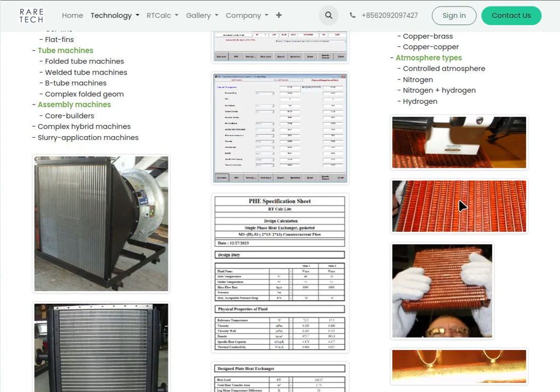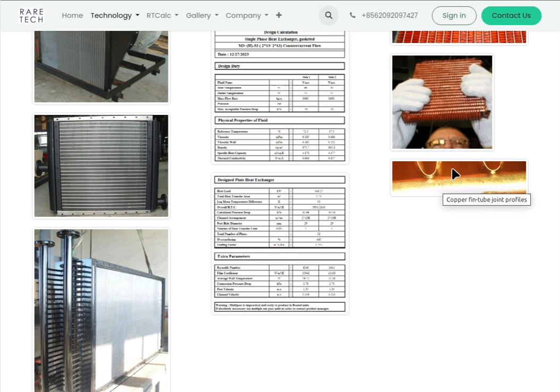What we're looking for is joint integrity. If you look at the joint profile, copper is a funny thing - depending on the alloy you're using, you can end up forming a bronze, and bronze has lower thermal conductivity than the copper itself. So you've got to be careful what you do there, and the joint itself has to be precise - you don't want a big thick joint like this, because you get very poor heat transfer.